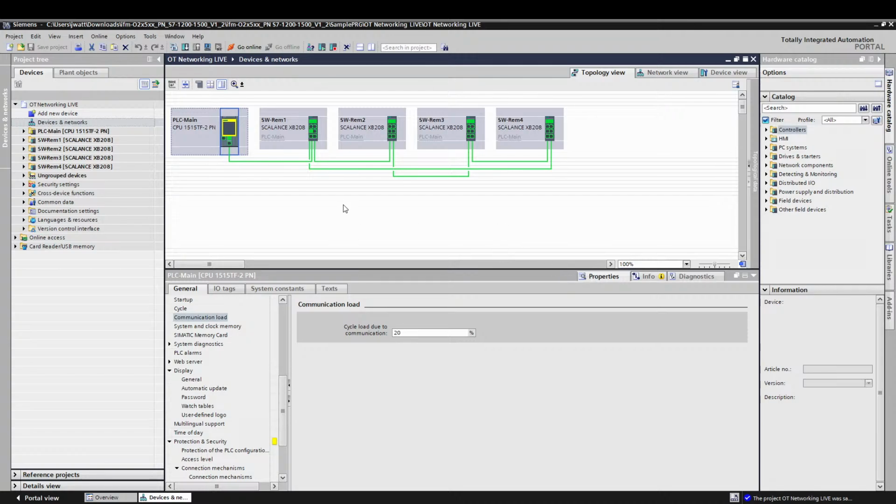And that is how you can actually tell where you have a fault on a cable in a ring network. In a star network, if you have a fault on a cable, like if a forklift runs over your cable, then this whole node is going to go down. Well, in a ring, that node's not going to go down, but both sides of it in this topology are going to be complaining about, hey, I don't have a partner on my port. It'll say partner not reachable, partner port not reachable. So if you don't have that, then you're kind of out of luck.